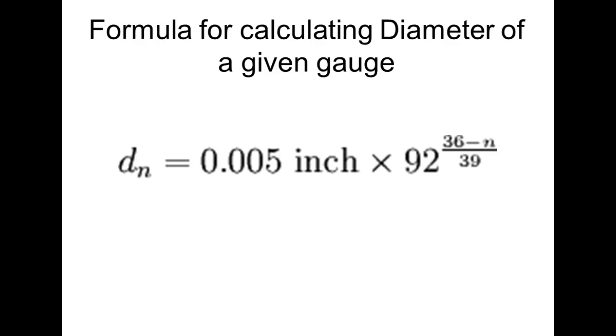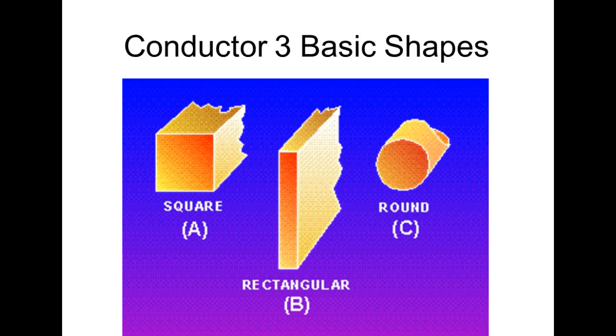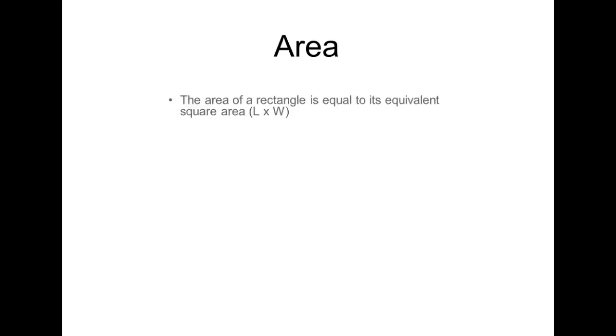It was very strange when I first got into the field. Normally when things get bigger, what they represent get bigger, but that's false in the American wire gauge. In the American wire gauge, the bigger the gauge number, the smaller the wire, right? We talked about circular mils. It's very popular to rate. Anything above 4/0 is going to be surely rated in circular mils.